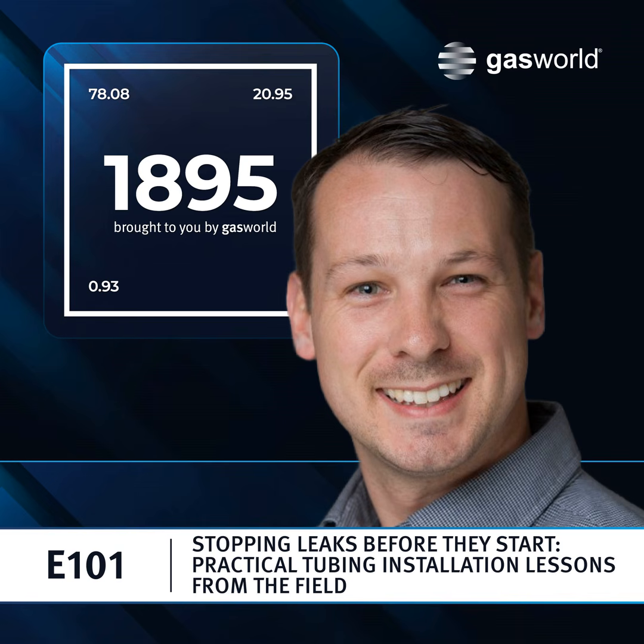If and when we do have to break into the fittings, certainly from a Swagelok perspective, we advertise that our fittings can be remade multiple times over and over again. So there's no issues with that. But we do offer something called a re-verification gauge, as do other manufacturers, and those can be used by your inspection team to test whether a fitting has really progressed beyond its useful life.